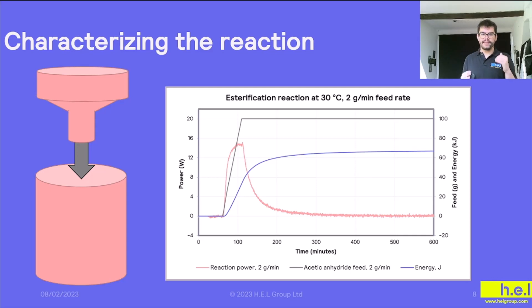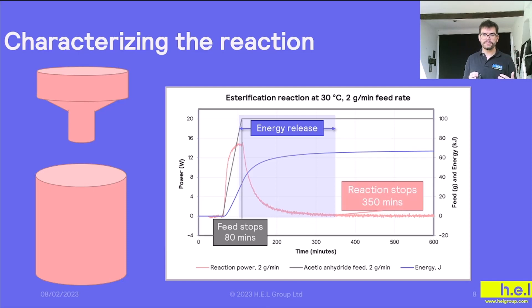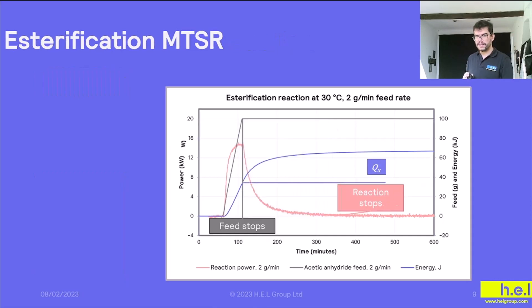So if we look at the graph we have on the right-hand side, we are going to see that the feed is going to be the gray line, and at some point we're going to stop the feed - in this case at 80 minutes - and we can see that the blue line, which is the energy accumulated in the reactor, is going to carry on accumulating even though we stop the feed, and it's going to carry on accumulating until 350 minutes. So this energy release is going to be very important because it's going to determine what our qx is and what our adiabatic temperature rise is going to be, and we can calculate it as we can see on this other slide.